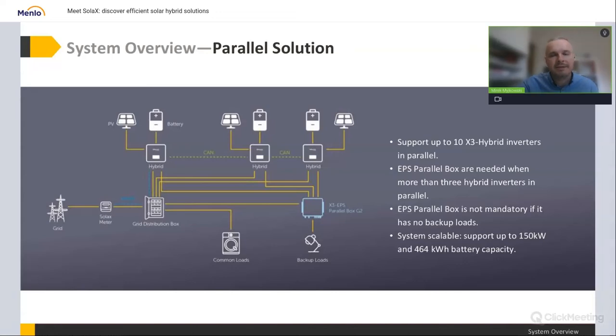Connected together into one system. Of course, every single inverter should have its own batteries, and they should be the same number and type of batteries to make it run smoothly. I've heard of many situations where there wasn't an equal number of batteries—you can manage that for half a year or a year, but then something may start to happen.